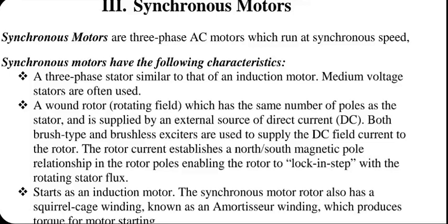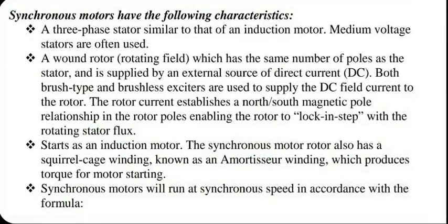Bullet number 2 is also reasonably clear, I think. Starting is done by making it an induction motor in the beginning and then letting it become synchronous as it picks up speed. Or the other method is to give it an initial mechanical push. We have seen that in the previous slide.